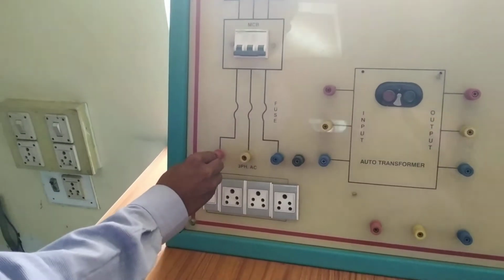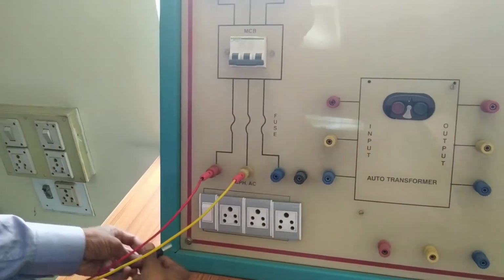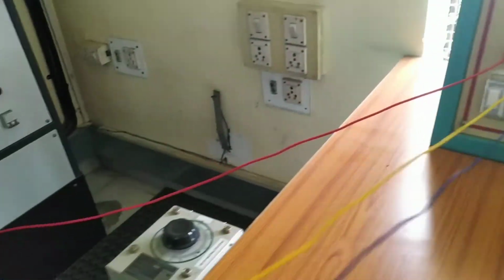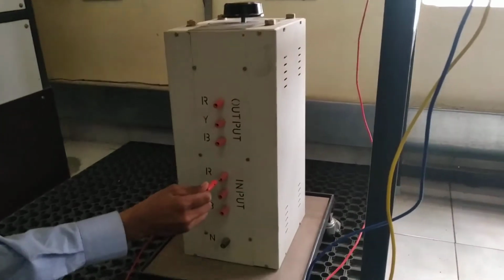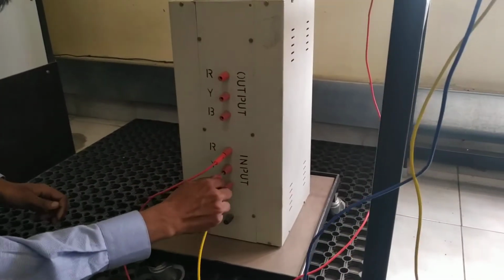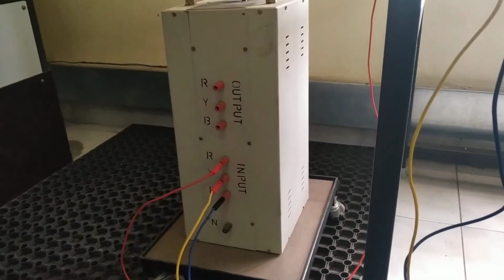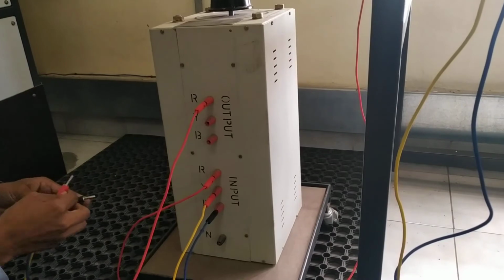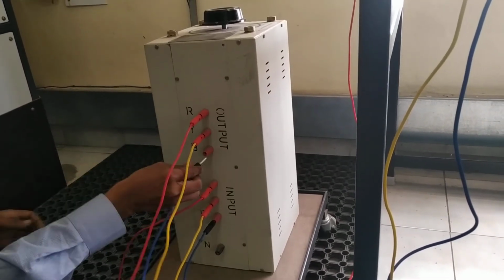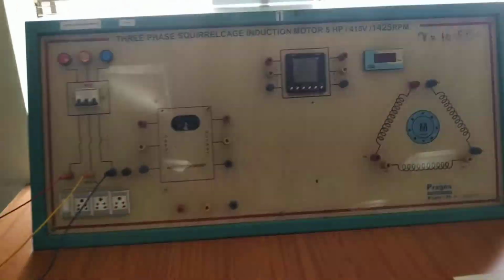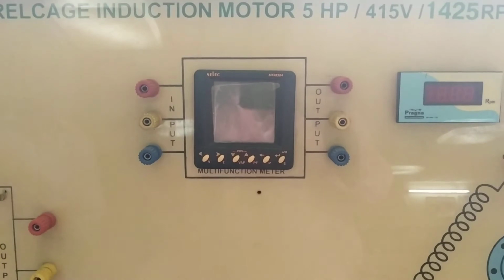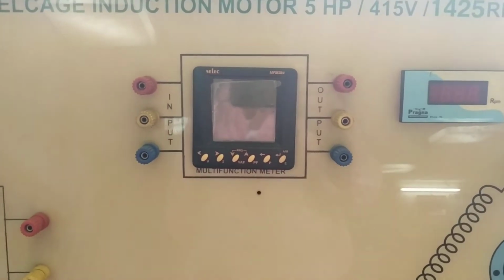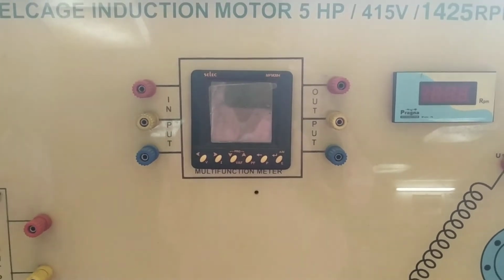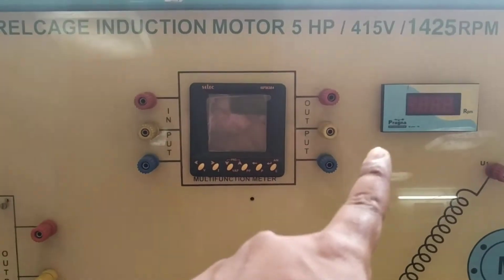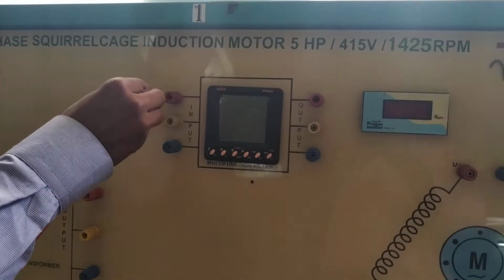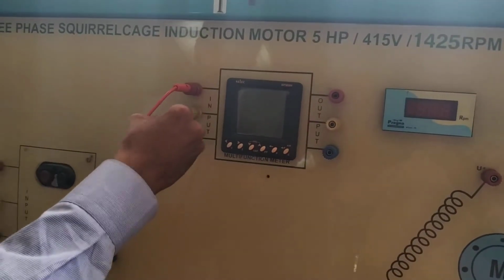From the mains, the RYB terminals are connected to the auto transformer. Respective colored wires can be used to make this connection. RYB should be connected to the input terminals RYB of the auto transformer. Again, the output RYB should be taken from the 3-phase auto transformer, and these 3 terminals are given to the multimeter. This is a multifunctional meter, where the line voltage, phase voltage, current, power and power factor with which the machine is running can be read. It also has 3 input terminals RYB and output terminals RYB. The output from the auto transformer should be given to the RYB terminals of the multimeter.